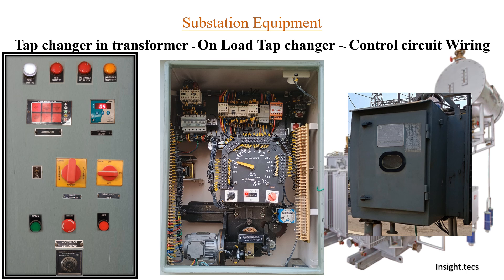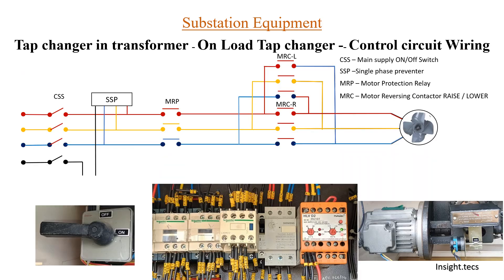Based on the operation of this motor, the tapping in the transformers will be changed. This is the entire mechanism that helps in changing the tap positions. This is the RTCC panel situated in the control room — remotely, using this panel, we can also change the tapping positions in the transformers. In the previous video we have already seen the connections between the OLTC DM box, RTCC panel, and mechanism.